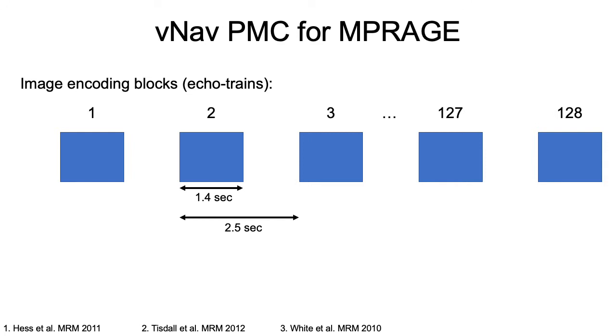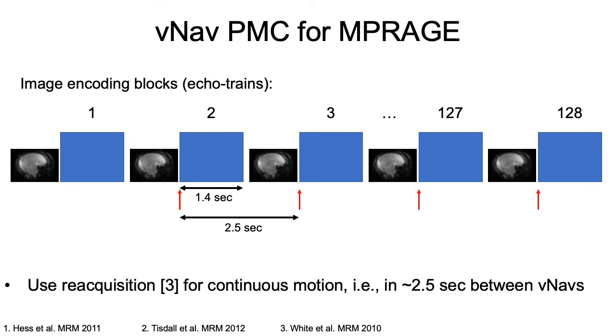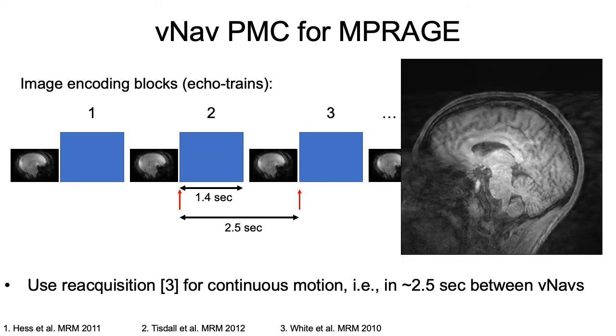This is a brief overview of the VNAV MP-rage sequence. In the gaps between image encoding blocks we can insert these low-resolution VNAV images and use those to estimate head motion, then update the field of view position before each image encoding block. Because the VNAVs are only acquired every 2.5 seconds there can be uncorrected head motion between the VNAVs, and we can use reacquisition to deal with this by reacquiring the TRs with the most motion at the end of the scan. This video shows how adding those reacquired TRs improves image quality.